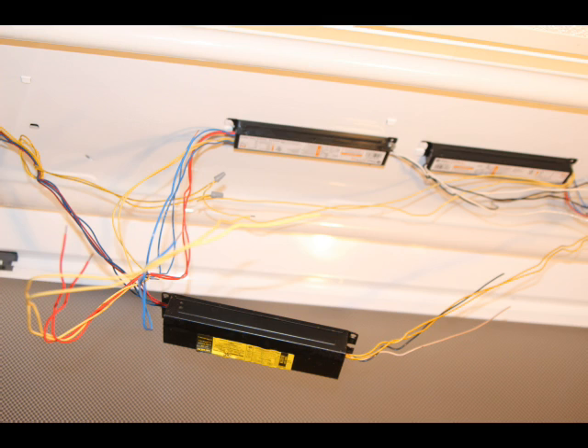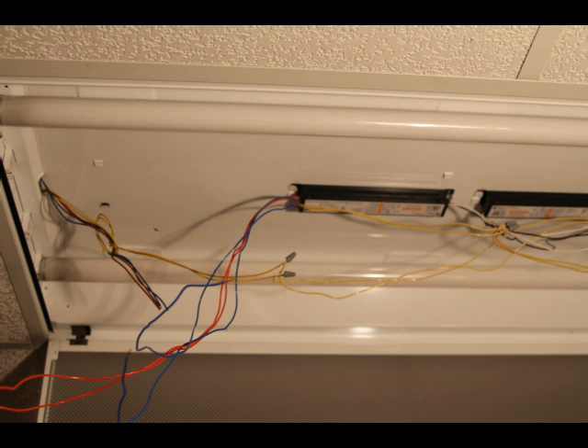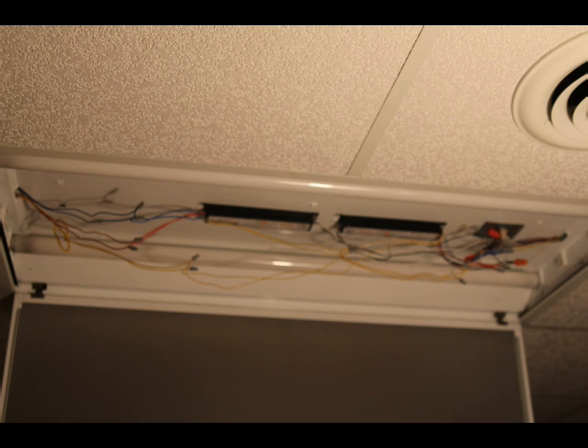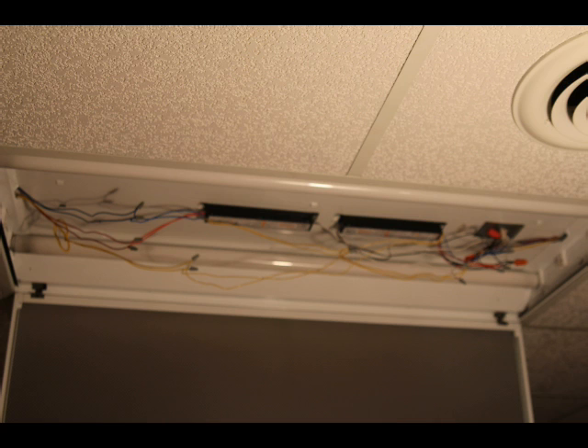Using the same system as the first, I dropped the old ballast, leaving it still connected to its eight various wires, screwed the new ballast up to the top of the fluorescent fixture, then, one by one, clipped and spliced the wires using the gray wire nuts. All of the wiring connections are made now, and all that is remaining to be done is to tuck the wires up underneath the U-shaped cover plate, and clamp that cover plate into place.